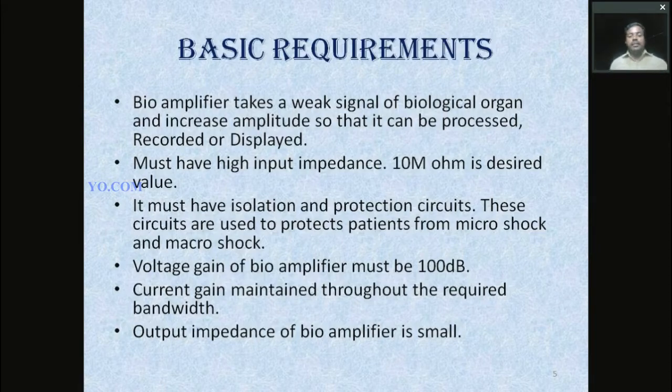Similarly, in the rainy season, the borewell produces some leakage of current that creates a shock. In the same way, if some high voltage flows to the low voltage side, it will affect the patient in the form of microshock and macroshock. To avoid that, we use isolation circuits. That is the second requirement.